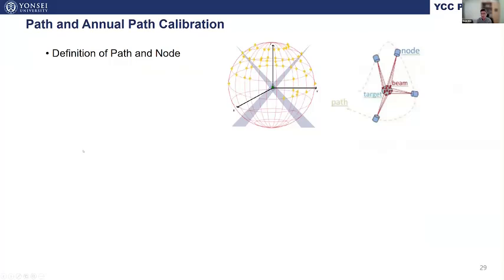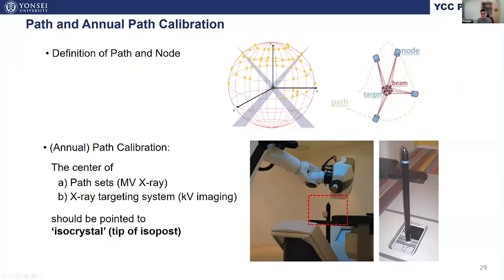To remind, the nodes are located within the workspace as mentioned earlier. A new concept, path, is defined as a designated route connecting these nodes. So a calibration of the path is required in the process of annual QA to make sure that the central path is exactly pointing to a reference point known as isocrystal. That is the tip of the isopost, the physical isopost, as illustrated here.